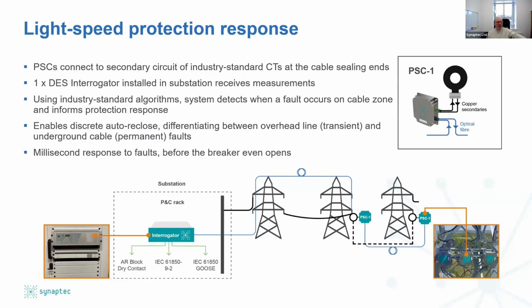Back in the substation, you've got our interrogator probably living in the relay room in the protection and control rack, and it's reaching out along the fiber outside the fence, maybe running 10, 20, 30, 40 kilometers away, and suddenly there's a cable section in the circuit. What we can do is install 3 current sensors at the first transition point, nearest, if you will, and another 3 current sensors at the furthest point away. And then by measuring those 6 currents, we're able to create a protected section. And all of that information is continuously, permanently, and synchronously made available by the interrogator to the protection scheme in the substation.